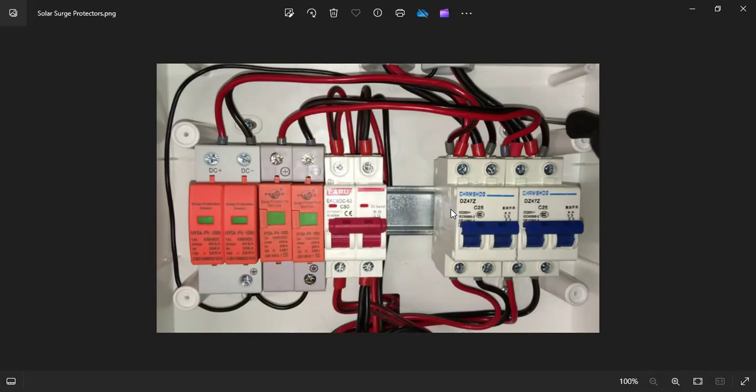You could see them bigger than the normal AC breakers, and they are even heavier than their AC counterparts of the same rating, mind you. The materials used in producing them are thicker so that they can withstand that constant amplitude heat generation. I don't know if it's clear.